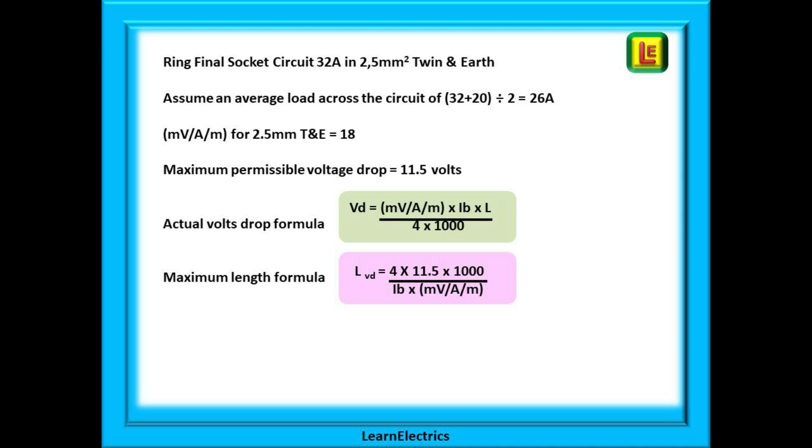So what have we done? We had a fully loaded ring final socket circuit protected by a 32 amp circuit breaker and wired in 2.5 millimeter twin and earth as recommended by the wiring regulations. We assumed the average load current by adding the full load current to the load at the furthest point and dividing this by two, which gave us 26 amps in this example. From the tables in the wiring regulations we know that the MVAM number for this cable is 18, and we also know from the regs that a maximum volts drop of five percent is permitted for a ring circuit, and this equates to 11.5 volts. We then used the appropriate formula to calculate either the volts drop or the maximum length for the circuit. Practice this a few times and it will become a powerful skill in your mental toolbox.